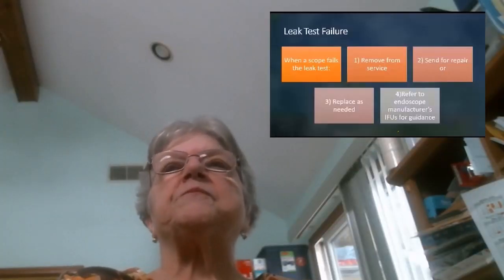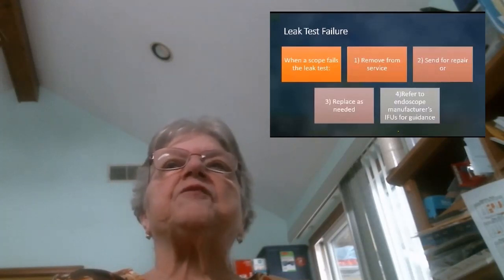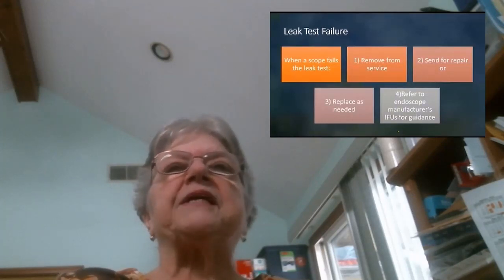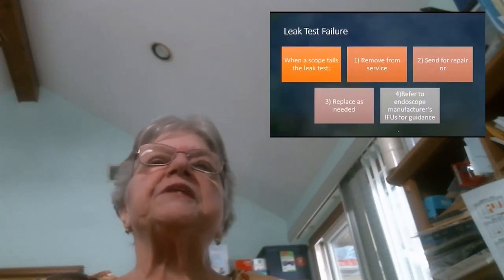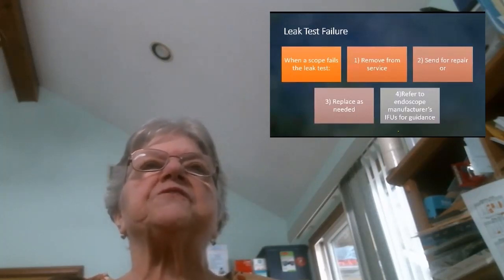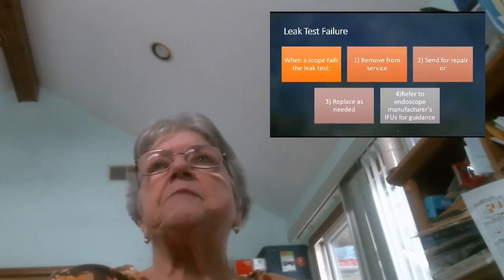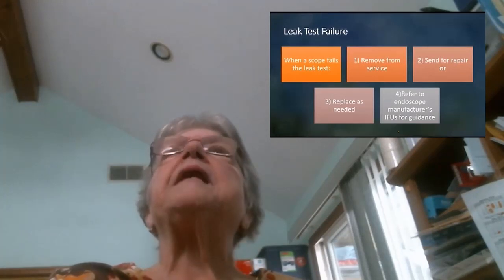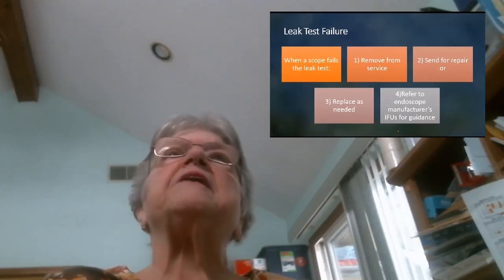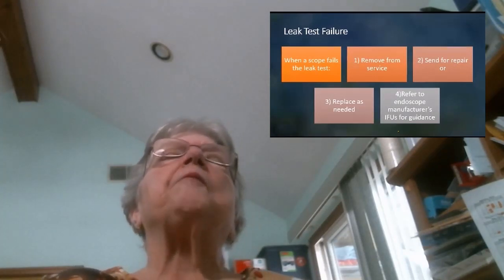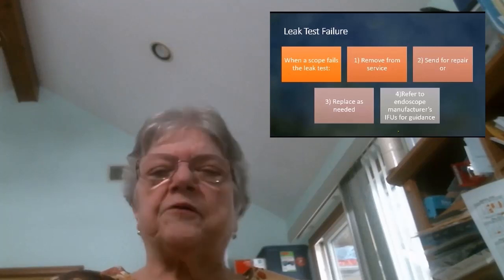1, you're going to remove it from service. 2, you're going to send it for repair, or you're going to replace it as needed. And you're going to refer to the endoscope manufacturer's instructions for guidance, because you can't send back a scope that you haven't been able to clean or disinfect. So your manufacturer will tell you what to do when you send it back to protect their workers from having an exposure.